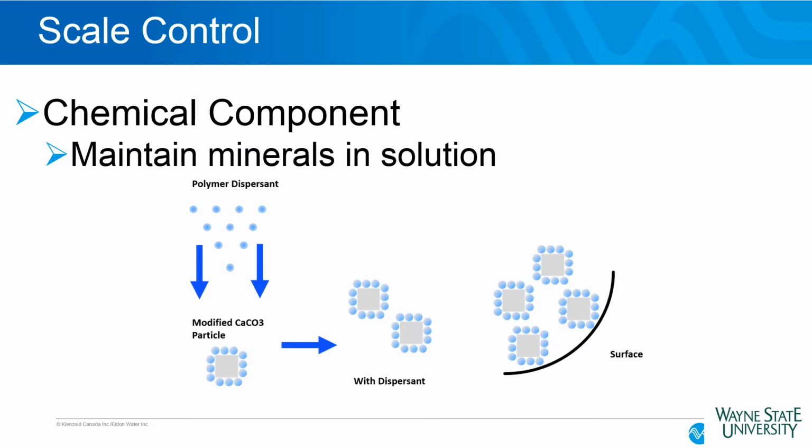And then from a chemical standpoint, what we add is what's called a scale inhibitor. Our Lo-Cor series, moving to the Monatrol series. More on that in a little bit. But you basically add a chemical in there that has polymers that bind with that calcium carbonate I talked about earlier and prevent it from sticking. When you bind with these crystalline structures, they just can't get a good grip on the surfaces, so they stay in solution and are bled out when the cooling tower blows down.